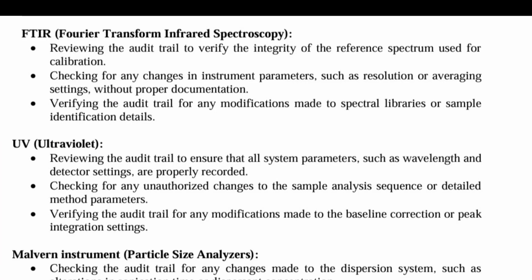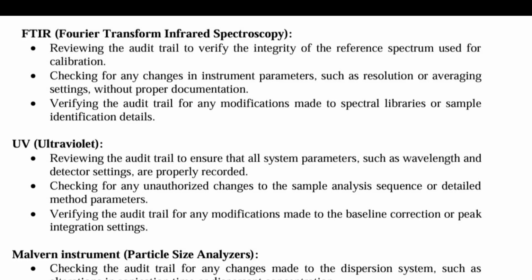FTIR. Reviewing the audit trail to verify the integrity of the reference spectrum used for calibration. Checking for any changes in the instrument parameters such as resolution or averaging settings without proper documentation. Verifying the audit trail for any modification made to spectral libraries or sample identification details.